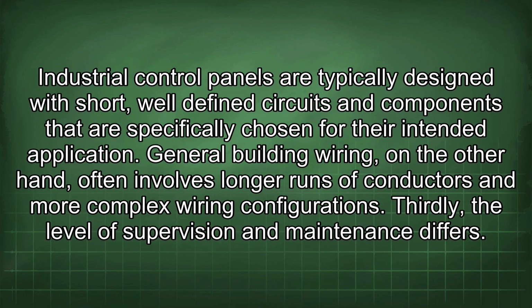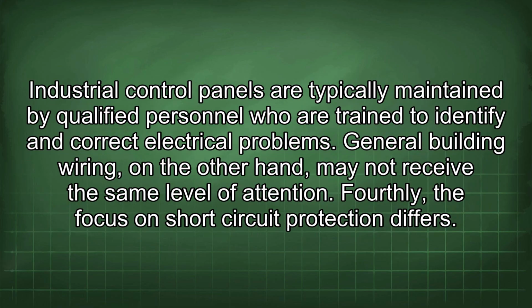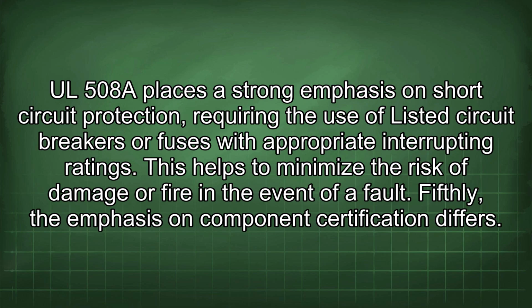Industrial control panels are typically designed with short, well-defined circuits and components that are specifically chosen for their intended application. General building wiring, on the other hand, often involves longer runs of conductors and more complex wiring configurations. Thirdly, the level of supervision and maintenance differs. Industrial control panels are typically maintained by qualified personnel who are trained to identify and correct electrical problems. General building wiring, on the other hand, may not receive the same level of attention. Fourthly, the focus on short-circuit protection differs. UL 508A places a strong emphasis on short-circuit protection, requiring the use of listed circuit breakers or fuses with appropriate interrupting ratings. This helps to minimize the risk of damage or fire in the event of a fault.